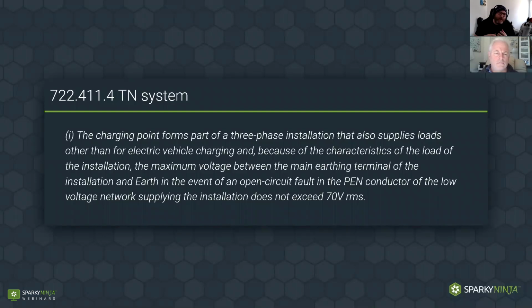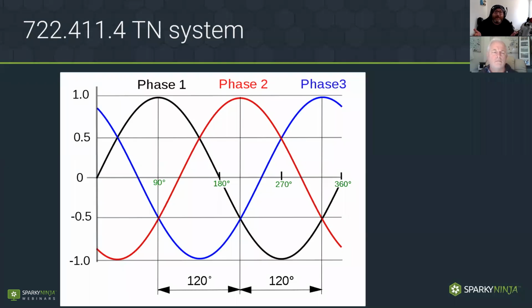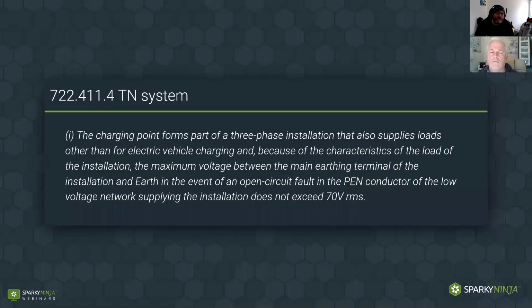So if we had a system where there were no currents in the neutral flowing, because the system was perfectly balanced in a three-phase arrangement, then in the potential absence of a neutral due to a broken PEN conductor, there technically wouldn't be any increased level of problem here. This is really just a regulation that's there because of the science, because it technically would work in theory. But the question is, how is that achievable, to actually balance loads equally on a three-phase system?